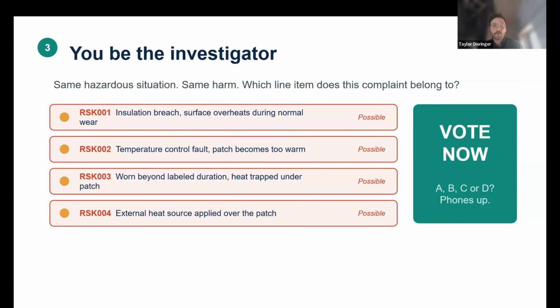So we could look at 4 different line items from our risk management file that include sequence of events: insulation breach, surface overheats during normal wear; temperature control fault, patch becomes too warm; RSK3, worn beyond labeled duration, heat trapped under patch; and RSK4 being external heat source applied over the patch.